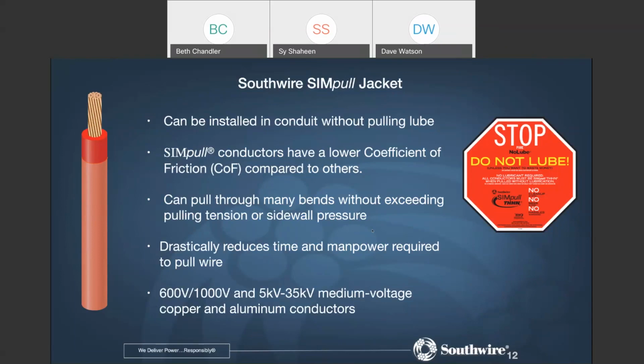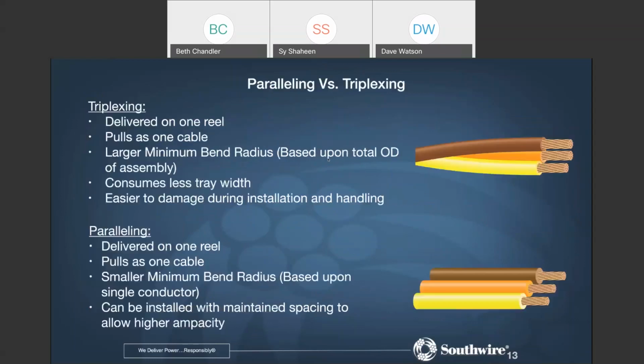That limitation was put into place years ago, primarily because of the friction that occurs when you try to exceed more than four 90-degree bends. And nowadays, with this low coefficient of friction Sim-Pull product, we can typically pull these through many more bends, but still need to comply with the code. But again, it allows you to put in a straight through pull box rather than having to actually pull it out and pull it back in. So it saves you labor and may save you some expense on the pull box as well. So this is going to help make the product much quicker and be able to install it at a lower cost.